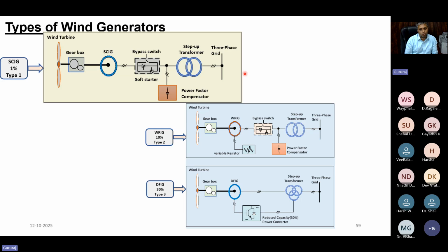Whereas in the type 2 generator, though you're going for a wound rotor, you're going for a physical, mechanical resistor. The point is you're going to use a physical resistor and a mechanical means of changing its resistance values. So though there is accessibility at the rotor side, not much speed variation is possible here. But the doubly-fed induction generator is the most popularly adopted. Even the biggest manufacturers like Suzlon, if you go to their portal and observe, have typical turbines of 2.1 megawatt capacity where they use these doubly-fed induction generator types.